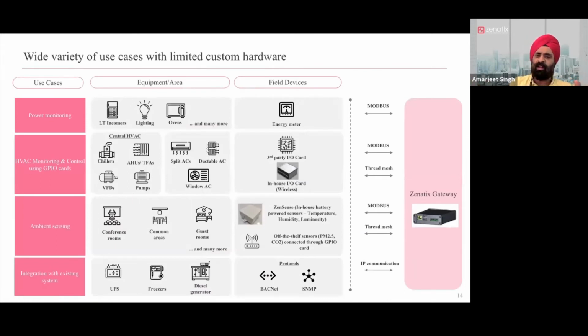Another beauty is that you don't need a huge variety of devices. You need a wireless IO card and a small number of battery-powered wireless sensors that serve your use case. If your use case is only temperature and humidity monitoring, you only need one type of sensor. If you want to add CO2, luminosity, etc., some sensors can connect directly to the IO card if they have a standard analog or digital interface, or be bought from us as battery-powered devices. With these two types of devices plus the gateway, you can connect a whole variety of HVAC equipment, whether a split unit, ductable unit, VRV system, or water-based system.